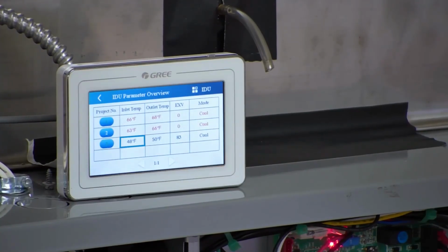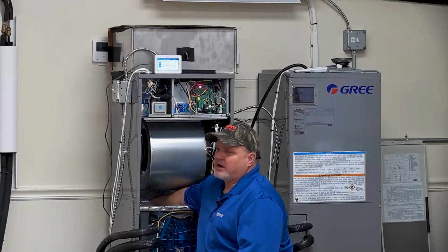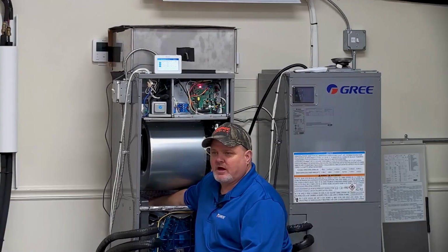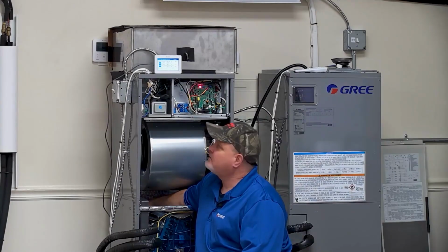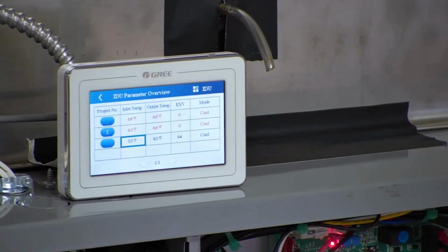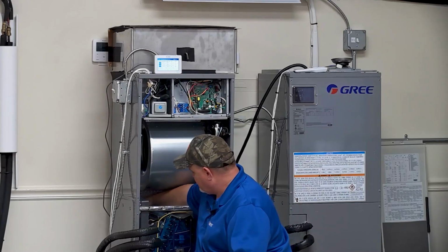48 degrees. Now we're going to go back the other way, start closing it back off. That's not going to make the machine very happy because it's the only unit I got running, we're going to be stopping our refrigerant flow. Yep, come back up, we're at 55 now. We're definitely starving it. You can see the frost kind of there because I'm stopping the flow.